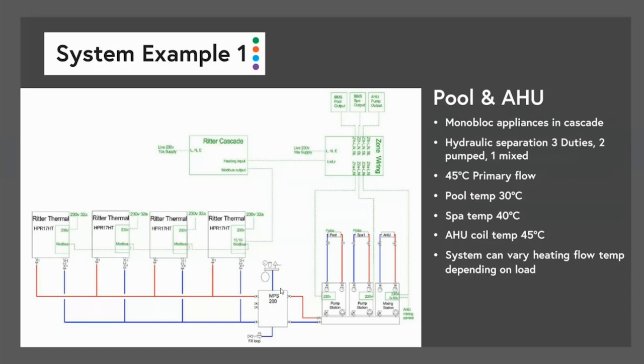It could be all sorts of things. You could include on there hot water production, you could include radiators, you could include underfloor heating. There's no real limit to what can be done in this sort of scenario. And we have controllers that will link all these units up, and they will produce heat on demand, and they will modulate between the units, and they will share the load. And so it acts as one system, but it's moving the load around and sharing the number of hours and all the duty cycling of the system.